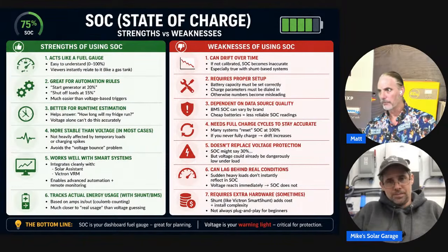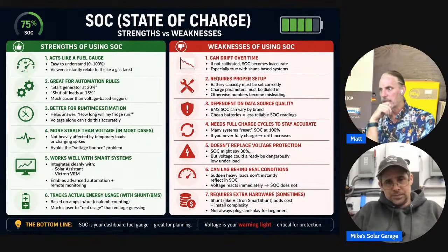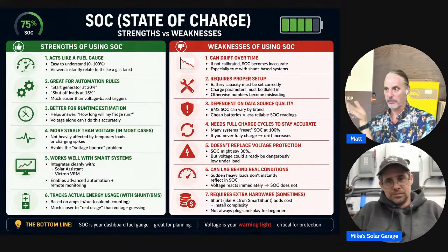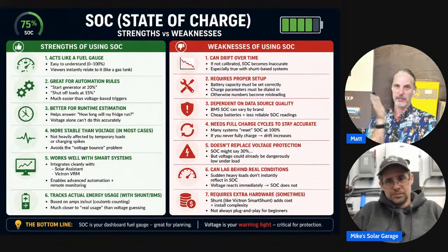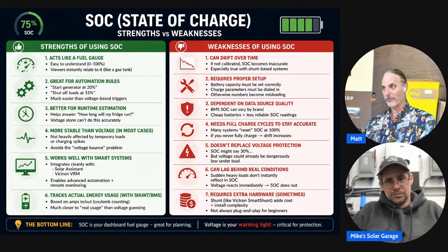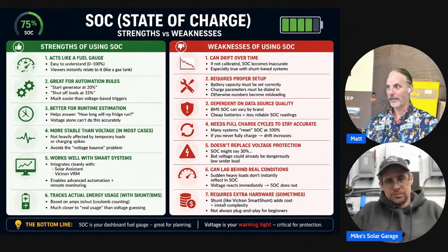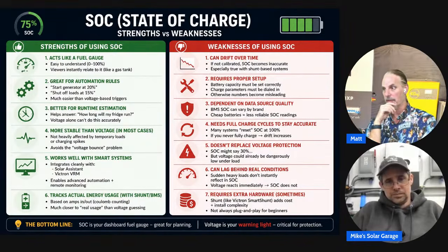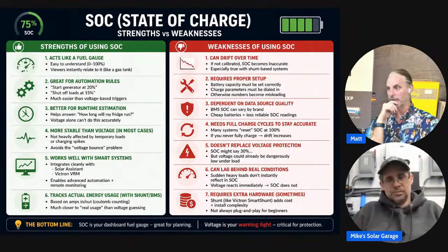State of charge might say 30%, but voltage could already be dangerously low or under load. This is one of the weaknesses of state of charge: you could be at 0% and still have 30% of your battery, or you could be at 30% and have 0% of your battery. The longer they go without top balancing, the more inaccurate they become. It's the butterfly effect in batteries.